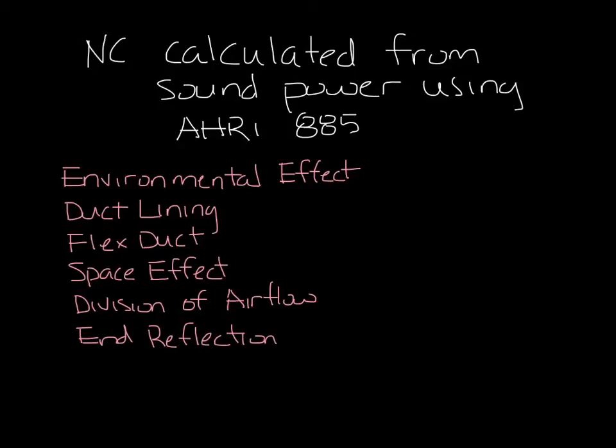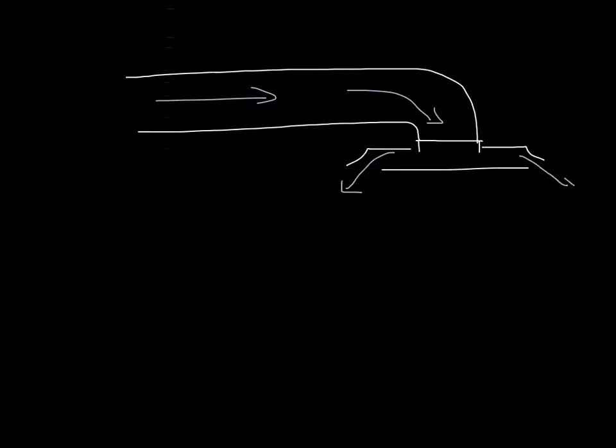Okay, so let's scoot this up and out of the way a little bit. As airflow goes down a ductwork and out an outlet, the air suddenly expands. Here's our ductwork and a diffuser, and the air is coming through here, it goes out the diffuser, and the air expands. This sudden expansion causes an acoustical phenomenon called EndReflection.